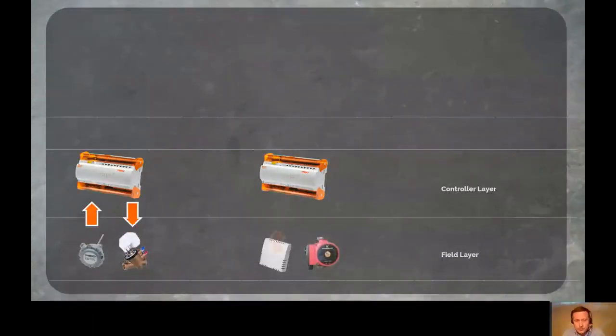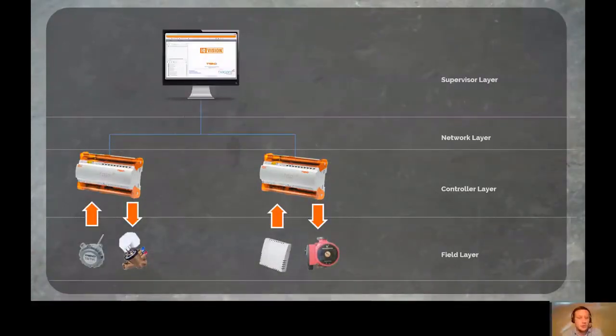You have what we call the field layer, which is physically the inputs and the outputs. So things like sensors and actuators and pumps, differential pressure switches, all of the field devices that are connected to the controller. You then have a network layer, which links the disparate controllers together, and then ultimately a supervisor layer, which is the visionary element.